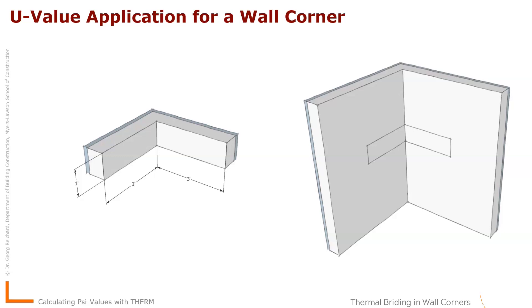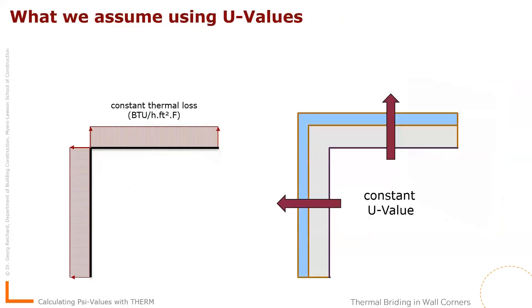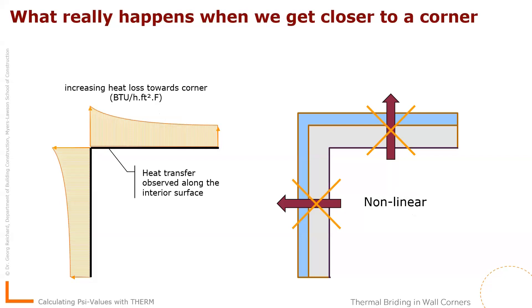So what we do actually here is we calculate the U value all the area into the corner, and that would assume that we have a constant thermal heat loss along the interior edge and this is actually not what exists. So what we have in this case is that because we have much more exterior surface on this corner, there is more draw in the corner and the heat loss will start slowly to climb the further we move into the corner.